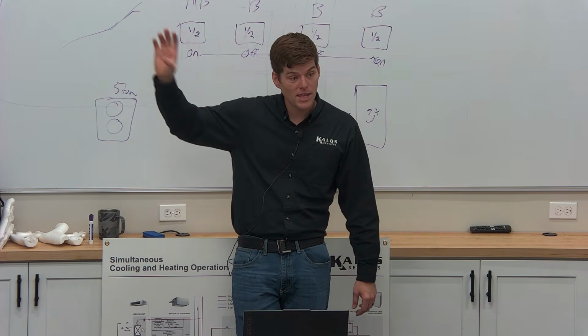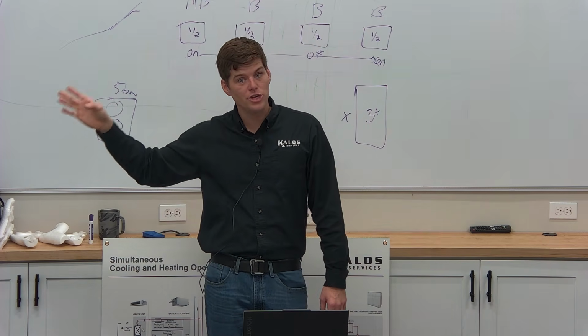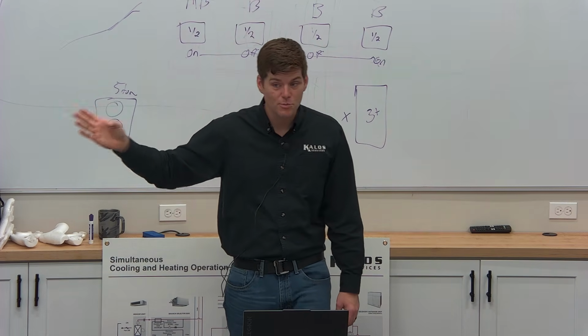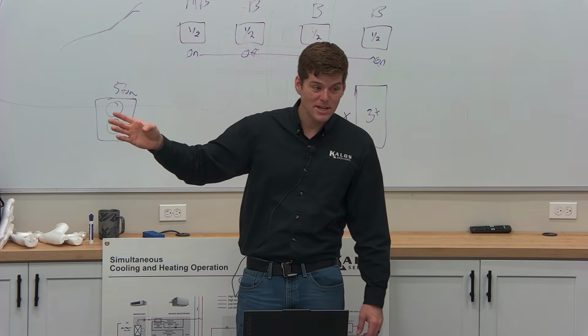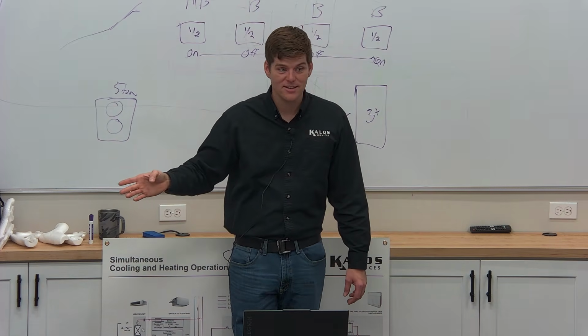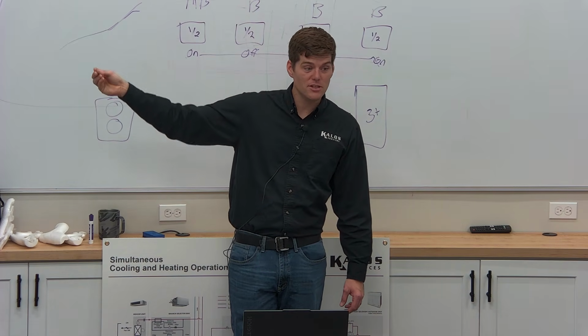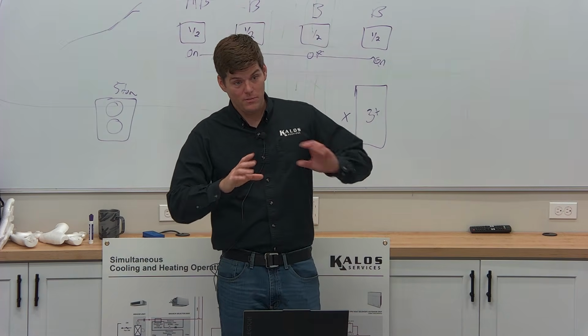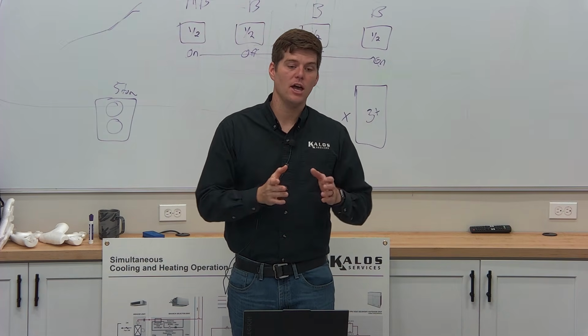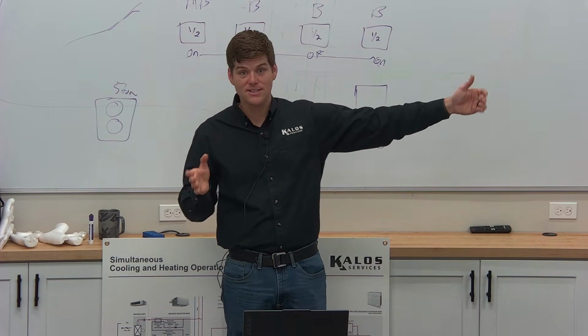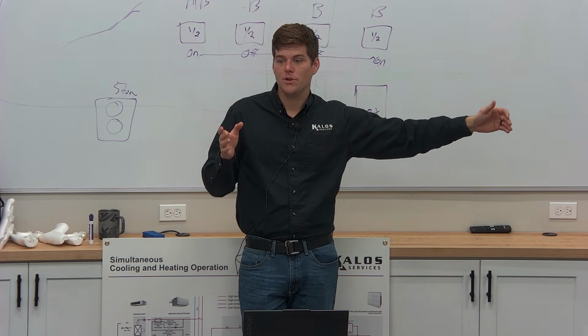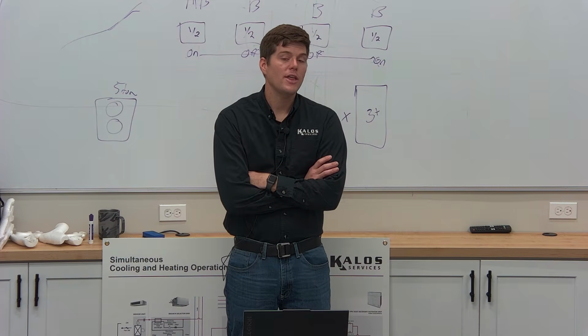And that gets put back into the report because the total charge added to this system isn't based upon superheat and subcool. It's based upon liquid line length and size. So you can't properly charge a system unless you know, without any doubt in your mind, that the liquid line is that exact distance and length. So measuring is extremely important. That's how critical it is, guys.